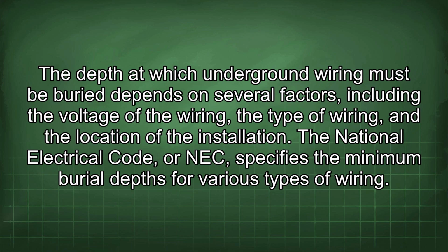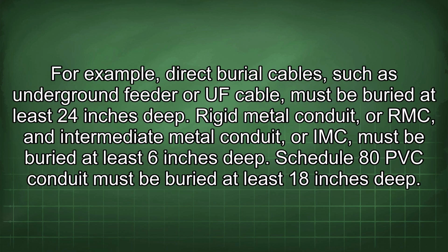The depth at which underground wiring must be buried depends on several factors, including the voltage of the wiring, the type of wiring, and the location of the installation. The National Electrical Code, or NEC, specifies the minimum burial depths for various types of wiring. For example, direct burial cables such as underground feeder, or UF, cable must be buried at least 24 inches deep.